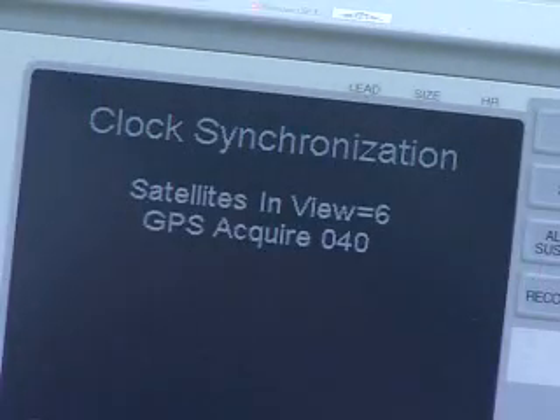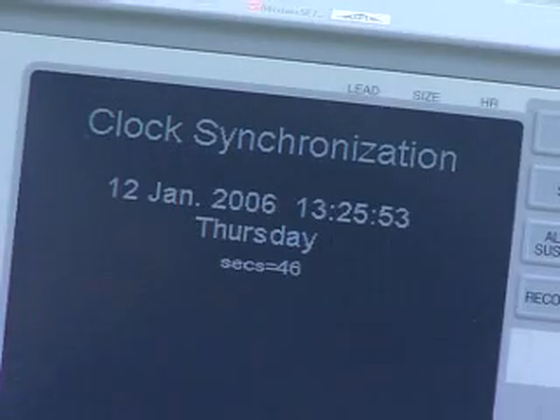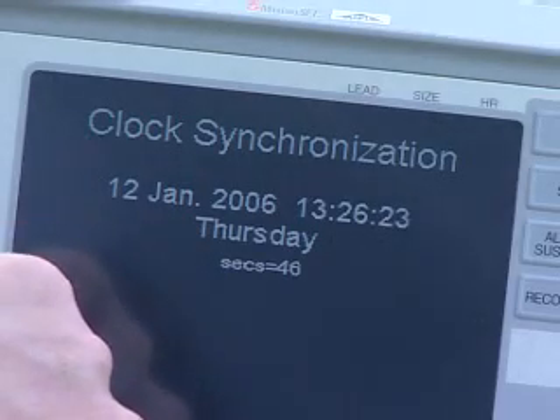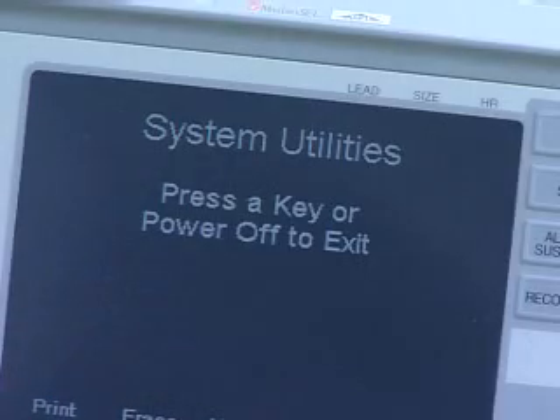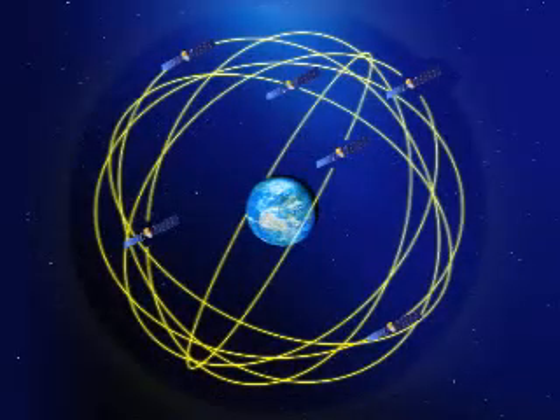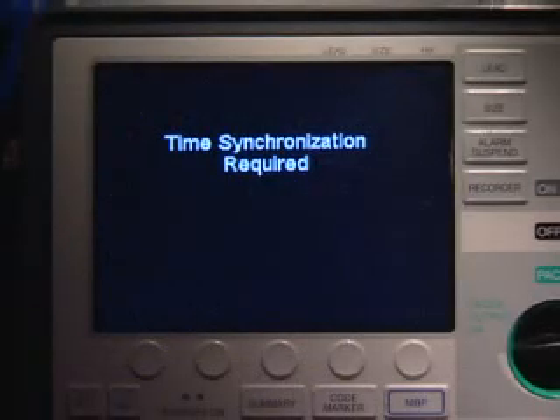When the GPS time has been acquired, the display will show the acquired date, time, and day, and the number of seconds needed to sync the clock. Press the Return soft key to store the acquired time and return to the main screen. GPS synchronization works automatically whenever the E-Series has a direct line of sight to the GPS satellites. If the internal clock has not been set within the last 2 weeks, the message Time Synchronization Required will appear when the E-Series is switched off.